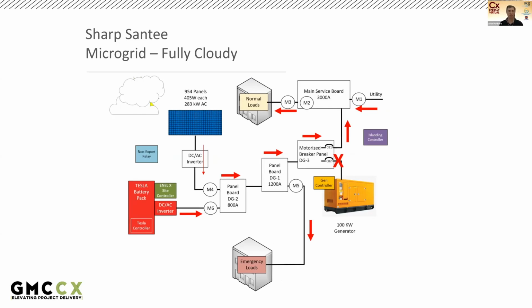Now, let's say it's a fully cloudy day. Obviously, here in San Diego, it never happens. I don't know why we'd even have to test this, but let's just say we've got a cloudy day here in San Diego, and we've got minimal power coming from the solar array, supplying power to panel DG2. Since it's not enough, and since it's during the day when we're on peak, the ENEL X site controller says, hey, it's a good time to use that stored energy in the battery. So now we're supplementing with power from the Tesla battery, sending that to DG2, to DG1, to the emergency load, sending it back up the chain to the normal loads of the building, and importing any additional energy we might need.